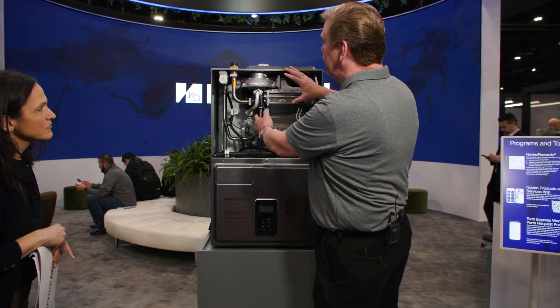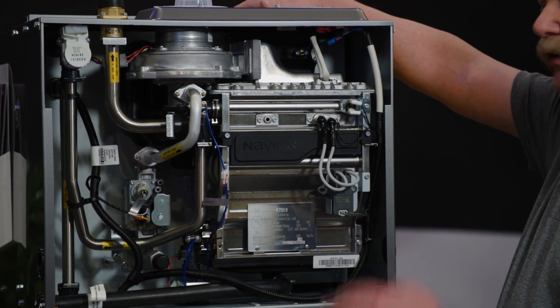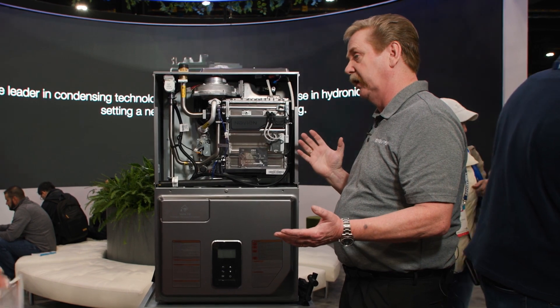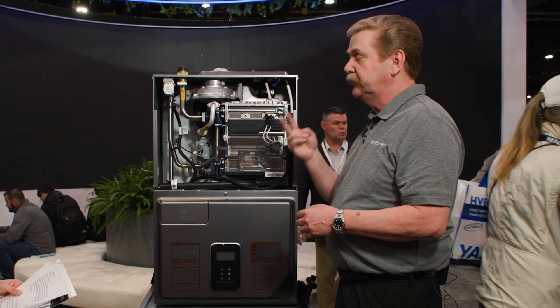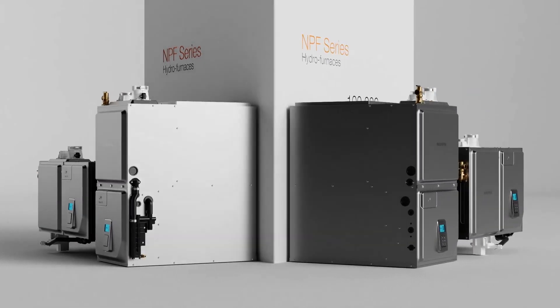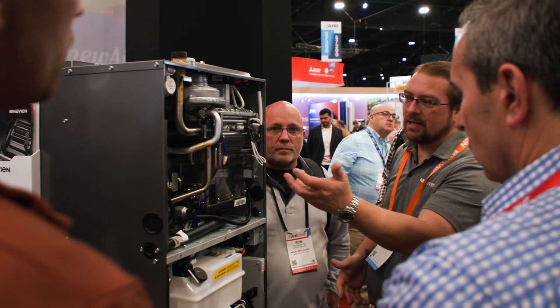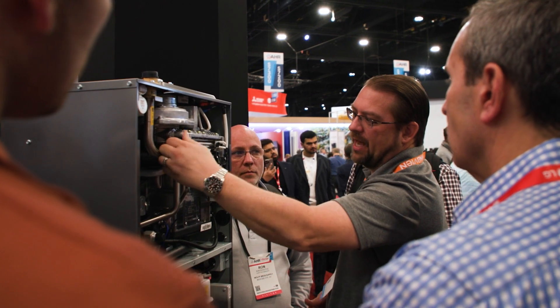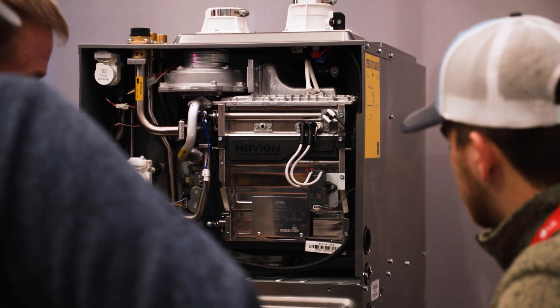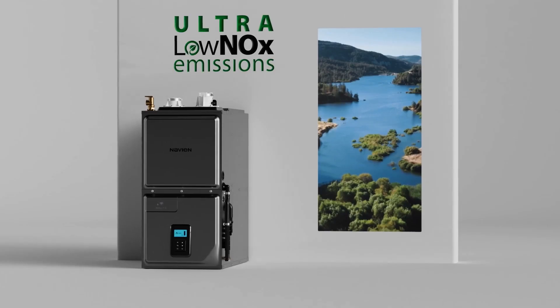By using our heat exchanger to heat hot water and circulate it through a fin tube coil, we're able to vary our capacity from 15 to 100 percent — a much larger range than anyone else in the market can do today. We have a 60,000 BTU unit that can go from 9,000 BTUs up to 60,000 BTUs, and a 100,000 BTU unit that can go from 14,000 up to 100,000 BTU. Robust airflow, all variable speed technology, all ECM technology — so electrically efficient. All models are 97% AFUE and all models are ultra low NOx compliant as well.